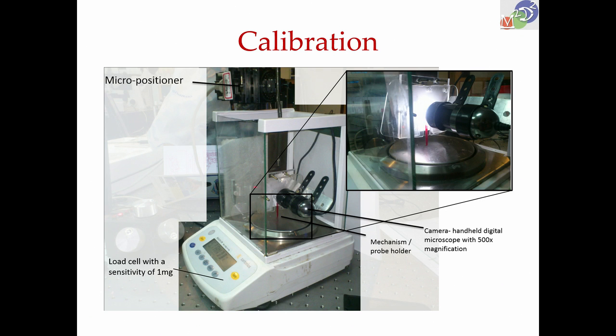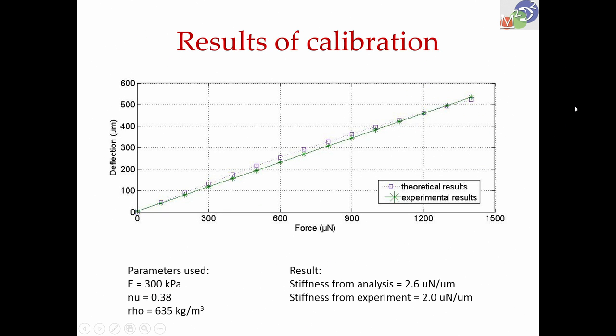even if you are using a weight in order to calibrate, that will change from place to place, because millionth-level changes in gravitational acceleration will be there when you go from one building to another building, or even in the same building, top floor to bottom floor, and different geographical locations. So, calibration here is quite tricky for these micronewton force sensors. Here we had a theoretical model with finite element analysis and the experimental result measured, and they are linear, they are not exactly coincident, but close. The stiffness, as I had said earlier, is 2.6 micronewtons per micrometer, and from the experiment we were able to see about 2 micronewtons per micrometer, reasonably close. This is theoretical, this is experimental.